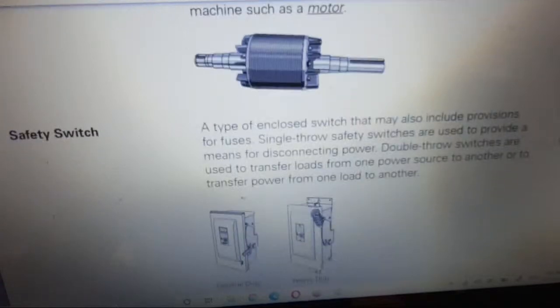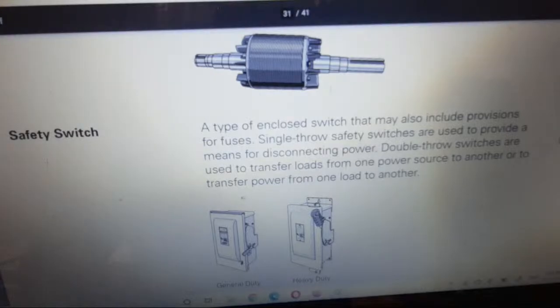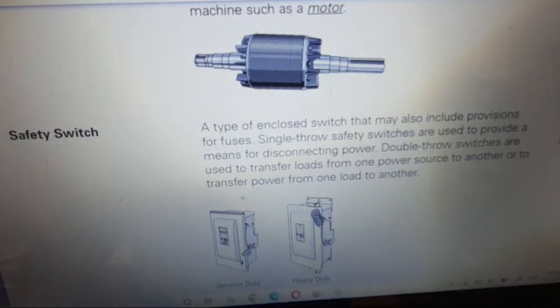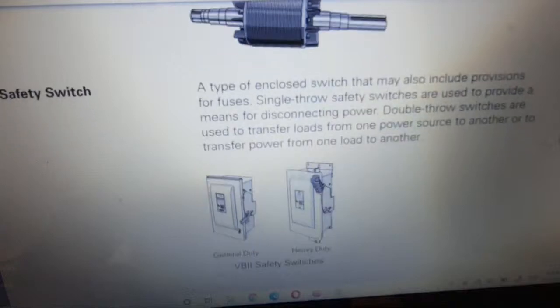Safety switch, a type of enclosed switch that may also include provisions for fuses. Single throw safety switches are used to provide a means of disconnecting power. Double throw switches are used to transfer a load from one power source to another, or to transfer power from one load to another.